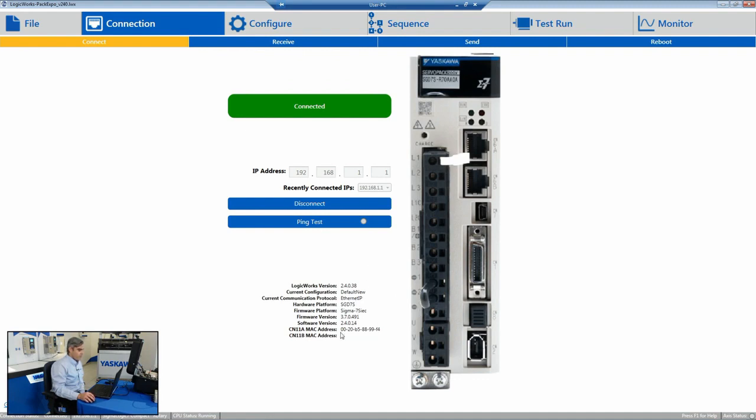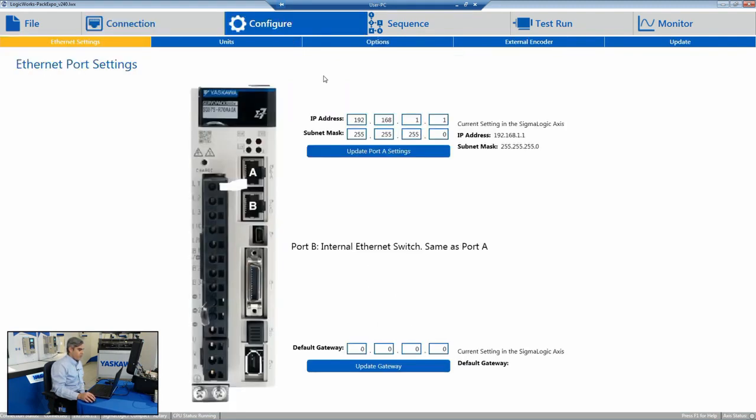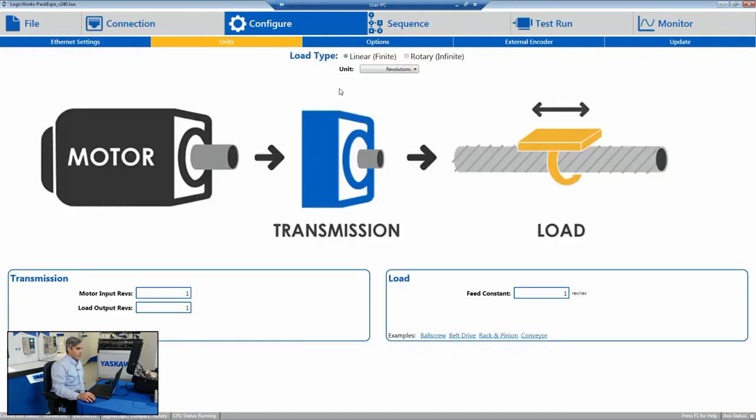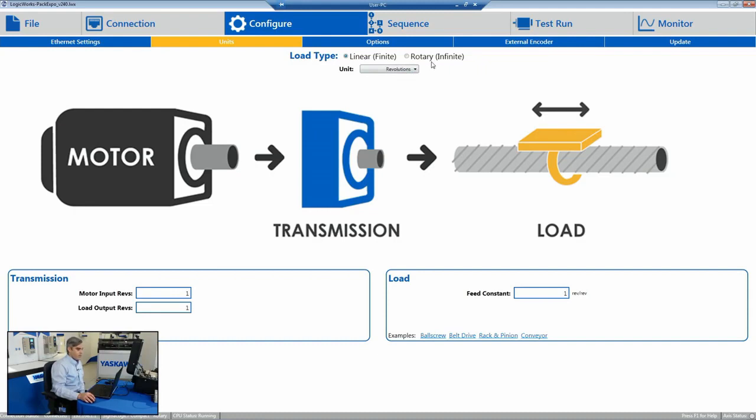So here you can check and confirm the versions on the hardware. You can configure units. So we work in real engineering units, whether that be revolutions, millimeters, inches. You can set it up for rotary axis as well, so you don't have to worry about encoder counts. It's all using real engineering units.